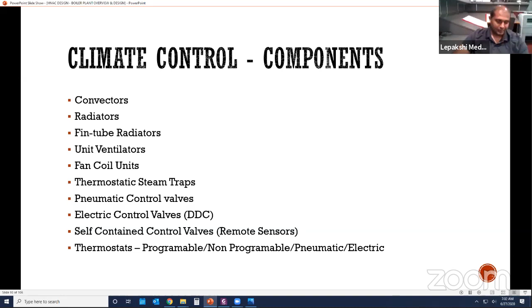And what are the components in climate control? You'll have radiators, convectors, fin tubes, unit ventilators, and whatnot. Let's talk about these real quick. What are convectors and radiators? I'm going to show you pictures of how they look, but what exactly are they? They are just like heat exchangers in that particular room. The steam goes in and exchanges its heat to the surrounding air, and the surrounding air gets heated up. The steam inside the convector condenses, and the condensate goes back to the system.